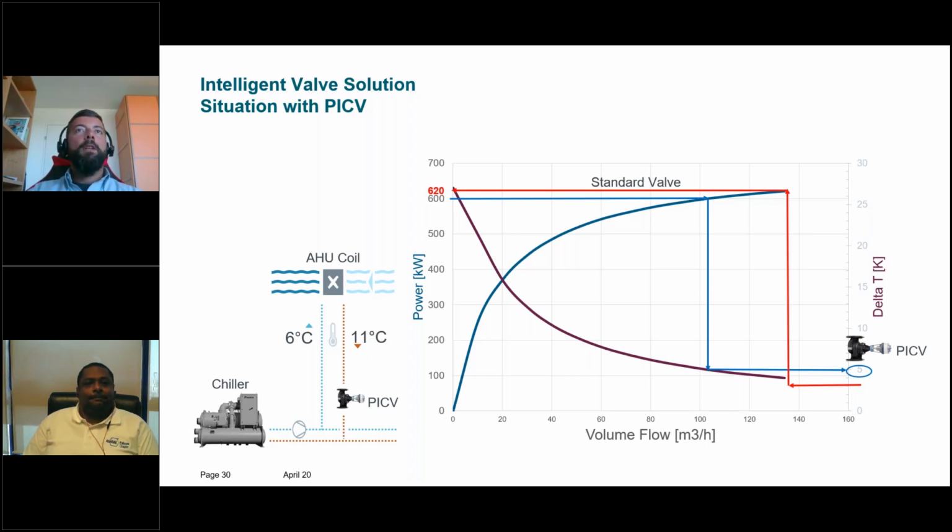Three-way valve system means constant volume systems, which means the volume of water supply in the building is always 100%, no matter the load required. I suggest having a look at this independent case study, because it also deals with the energy consumption of three-way control valve solutions. This is taken as a reference, like 100% consumption.